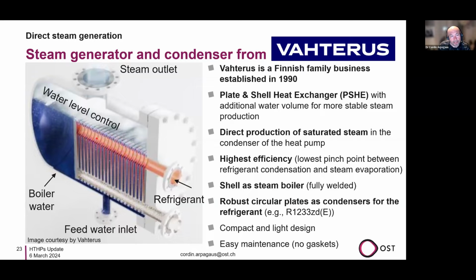So this is really direct heat exchange. This is, let's say, the most efficient way. There is no other media in between, so that's the smallest pinch temperature in this heat exchanger, which makes it most efficient. The shell is used as a steam boiler, and it is fully welded and very robust. These plates are in a circular shape, also welded, in a very compact and lightweight design. These heat exchangers can also be cleaned very easily. There are no gaskets, so it's a very robust system, used especially in these steam generating heat pumps.